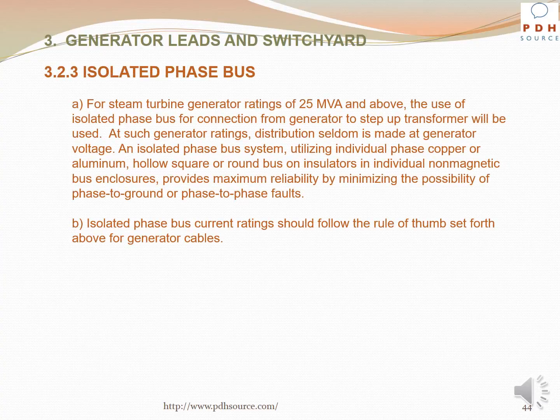With regard to isolated phase bus for steam turbine generator ratings of 25 MVA and above, the use of isolated phase bus for connection from generator to step-up transformer will be used at such generator ratings. Distribution seldom is made at generator voltage. An isolated phase bus system utilizing individual phase copper or aluminum, hollow, square, or round bus on insulators in individual non-magnetic bus enclosures provides maximum reliability by minimizing the possibility of phase to ground or phase to phase faults. Isolated phase bus current ratings should follow the rule of thumb set forth above for generator cables.